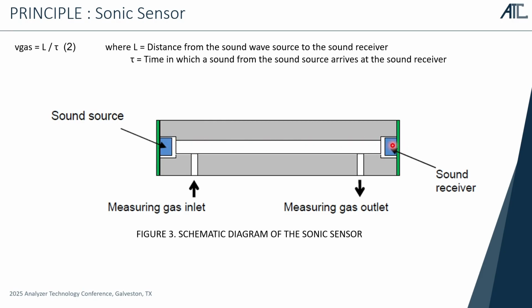And then this sensor measures the time the sound travels from here to here. And then if gas with a high BTU value is filled in the gas measuring chamber, the sound speed gets slower. So we monitor the speed of sound to measure the BTU value. And the same as the optical sensor, this sensor is based on physics, so no chemical reaction and no burning, so the sensitivity is quite stable as well.